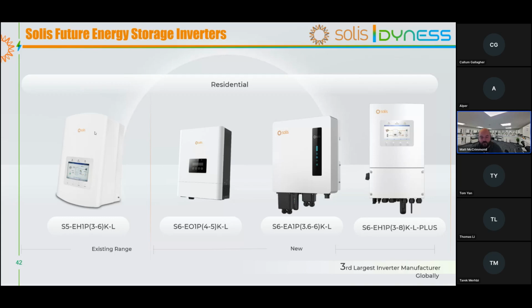We also have some new inverters that we're bringing to market. So starting off, we have a purely off-grid inverter. That's the 4 and 5 kilowatt unit that can be paralleled up to 6 units, so you can create up to a 30 kilowatt system. That's not going to be certified for any grid, so it's a purely off-grid application that has a generator port to charge the battery based on SOC, for example.